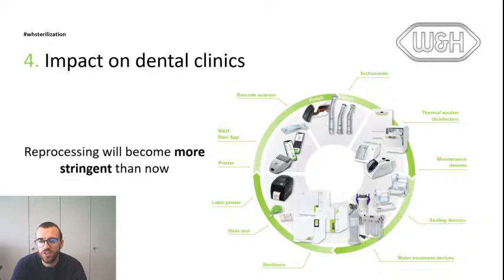As I mentioned before, sterilization can only be made in the right way if the instrument is clean. So if the instrument is well cleaned, the sterilization works properly; otherwise, it's not possible to sterilize in the right way. So pay attention to the cleaning aspect to have good sterilization in the reprocessing room.